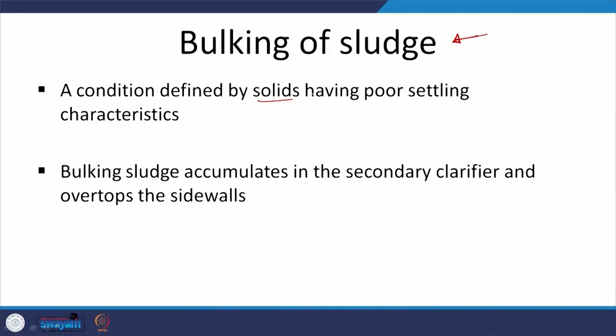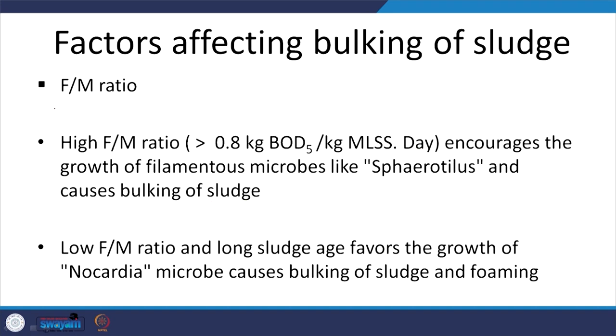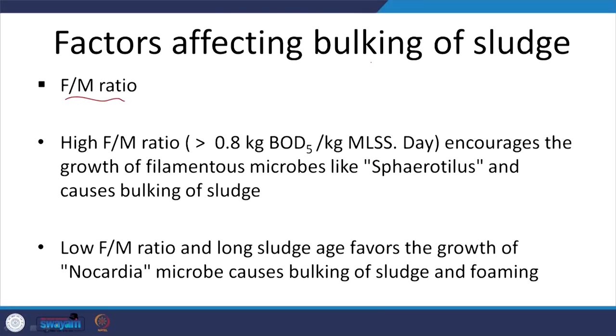Bulking of sludge is characterized by solids having poor settling characteristics; they accumulate in the secondary clarifier and can even overflow the side walls. There seem to be various factors that lead to bulking: it can be filamentous or non-filamentous. High F/M ratio encourages the growth of filamentous microbes like Sphaerotilus and causes bulking. Low F/M ratio and long sludge age favor the growth of Nocardia microbes, causing bulking and importantly foaming.